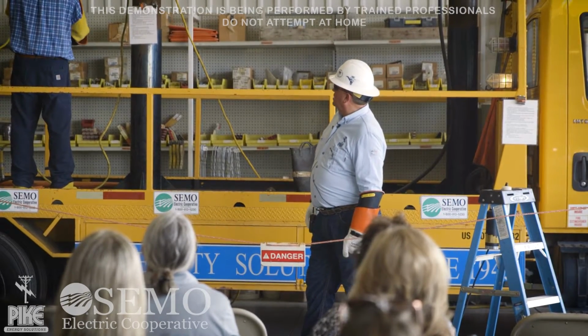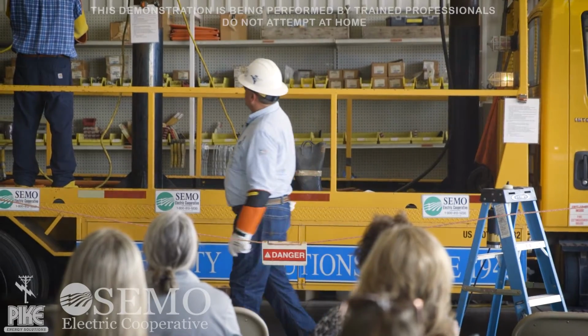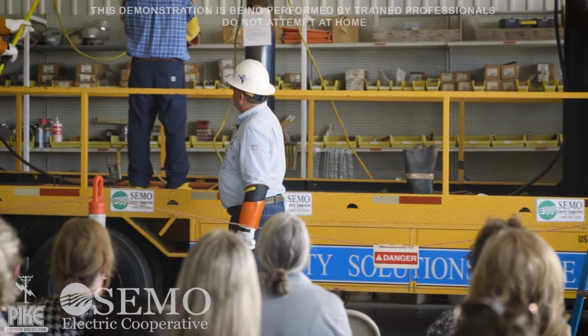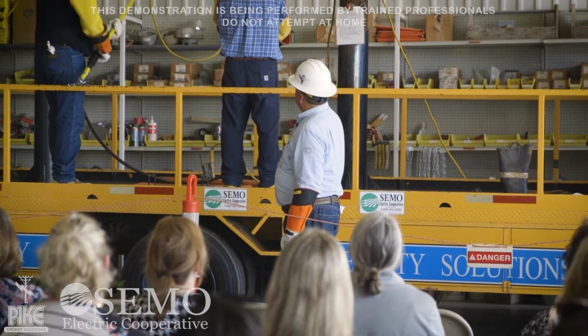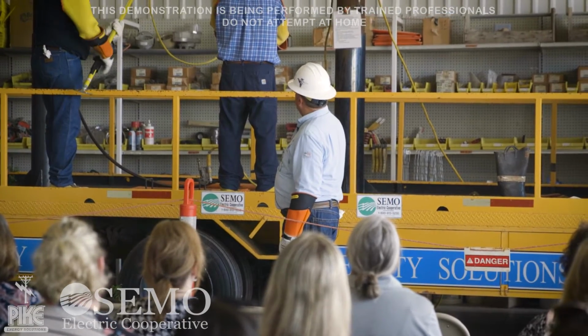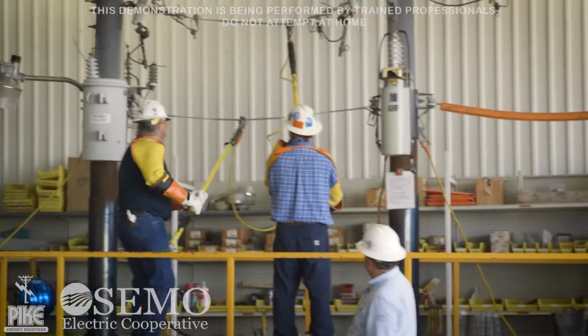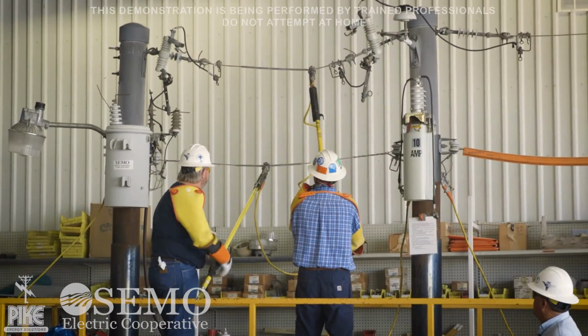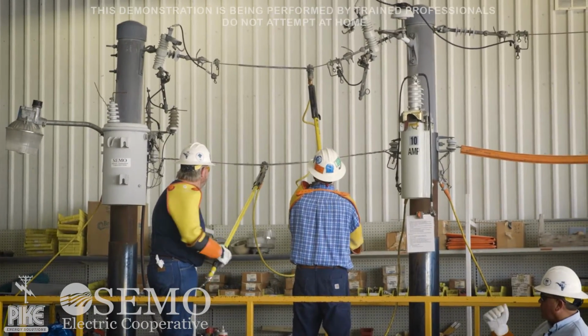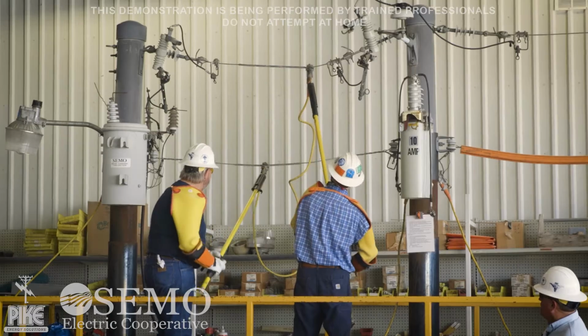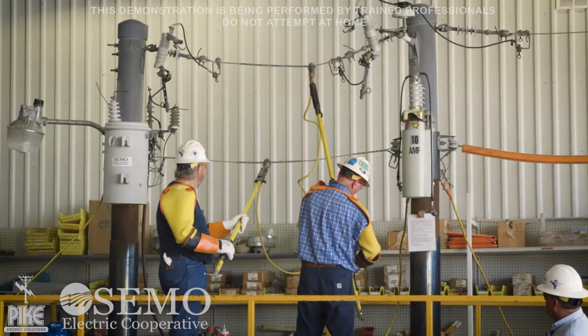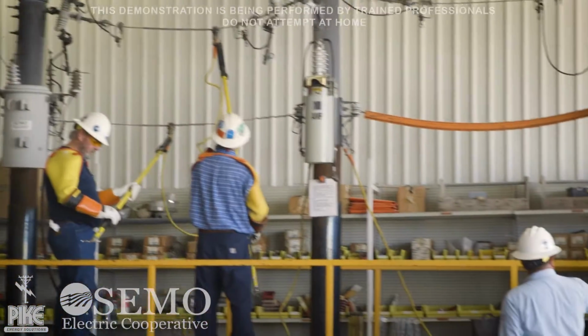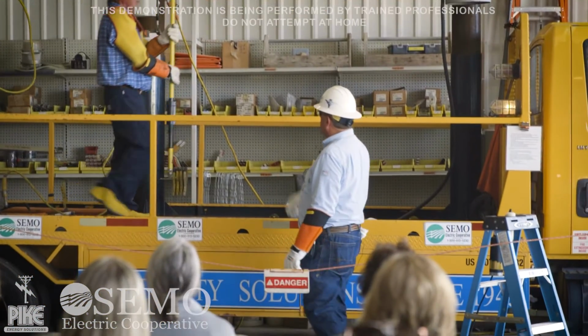So we normally go on the neutral first. Always go to your neutral first. Always make sure your grounds are good and tight, good and clean. Then we flag our grounds, and we also tag our recloser out.